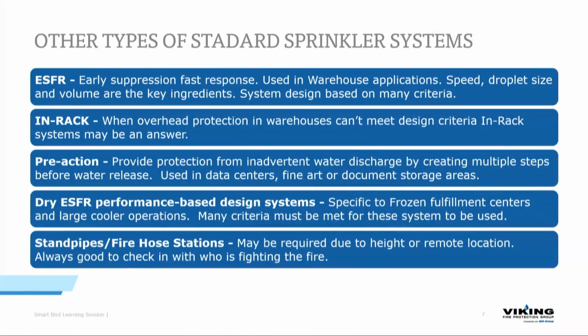tons of different system design criteria goes into it. We have racking height, building height, what you're storing. So there's a whole chapter that I really don't like to get into in NFPA that deals with this specifically, down to racking width, and ASRS is a whole other issue that we're starting to deal with as well with the ESFR systems. In racks, where our overhead protection doesn't really suffice in an ESFR situation, we may need to use in-rack fire sprinklers. And again, those are designed based on different criteria of what you're storing.